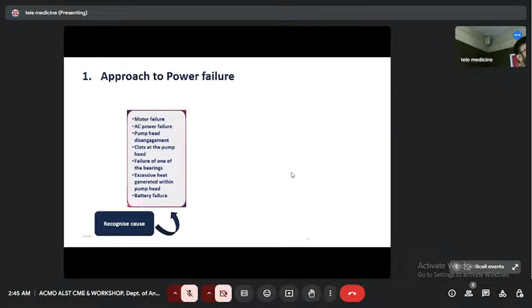What do we have to do in that condition? First, because most of it depends on the patient, you have to increase the ventilator settings and increase the inotropes and vasopressors. Stabilize the patient and divide the team among yourselves. Some will see the patient, some will go towards the ECMO machine. So the first things are: call for help, patient management, and hand cranking. One hand crank is kept near the pump. So we have to take the patient on ECMO, and you have to start the hand cranking. Previously you saw the ECMO flow and RPM and all those things; start hand cranking according to the RPM. We'll show this in the stations.